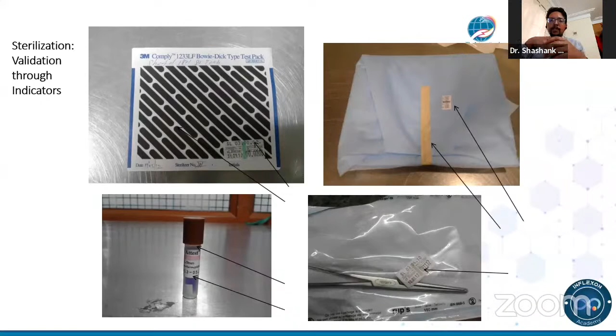The picture on the top left-hand side is the Bowie-Dick indicator, in case you're doing this through steam. If you have a vacuum-based steam sterilizer, please use a Bowie-Dick indicator. Again, I'm saying, only if you have a pre-vacuum sterilizer. This is not for manual steam sterilizers. Yeah, can we go on to the next slide, please?